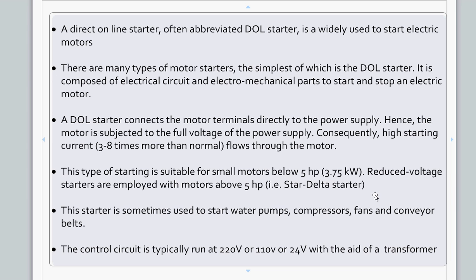This type of starter is only suitable for small motors, basically below 5 hp. Above 5 hp, it is better to use star-delta starter or electronic starters. This starter is sometimes used to start water pumps, compressors, fans, and conveyor belts. The control circuit depends on the coil—it can run on 220 volt, 110 volt, or 24 volt. In this case, you need to add a transformer to step down the higher voltage.